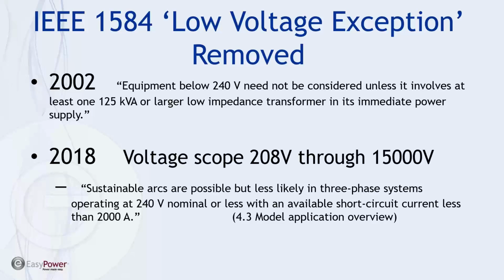And it turns out in the subsequent system testing that IEEE conducted, and other studies that were conducted by individuals and certain companies, it became clear that this wasn't in fact true. There were some loads that could have an arc flash hazard associated in this lower voltage category. So with the release of the 2018 version of 1584, they no longer have this low voltage exception. What they have in place is a statement, this is under chapter 4.3, and it suggests that sustainable arcs are possible but less likely in three-phase operating systems at 240 volts nominal or less with an available short circuit current of less than 2000 amps.